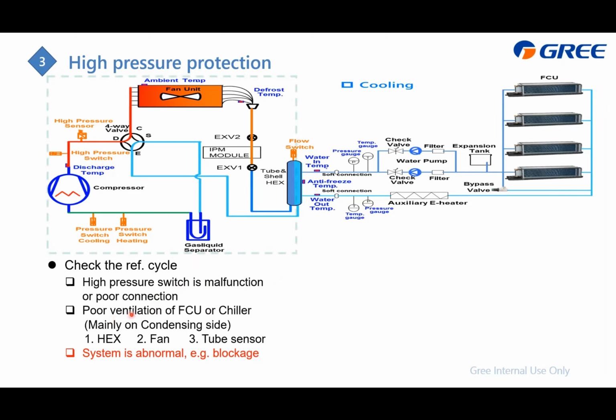And next is to check whether the FCU or the chiller on the condensing side, including the heat exchanger, the fans, and also the tube sensor, whether it's in good contact with the tube, or maybe the system is abnormal, just like the EXV is a blockage or stuck.